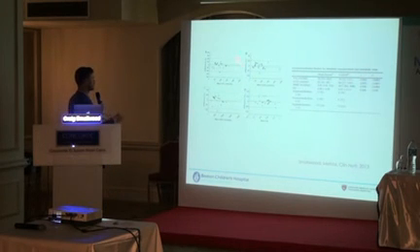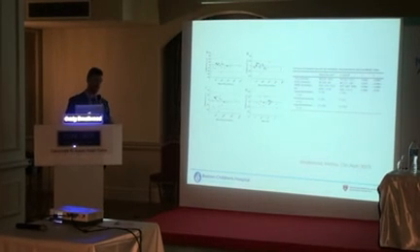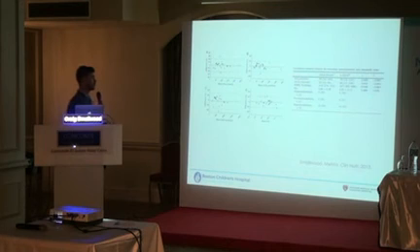You can see we enrolled 19 total subjects, and each one of these dots is one subject. For the overall mean VO2, this would be closer to an infant or a newborn down here. You can see that in this case it was minus 20%, so there was a 20% discrepancy. But there's a lot of heterogeneity in the overall population. So what we decided to do was say that these devices weren't equivalent. In some cases, for CO2 they were, but for VO2 they didn't seem like they could be compared to each other with 100% confidence.